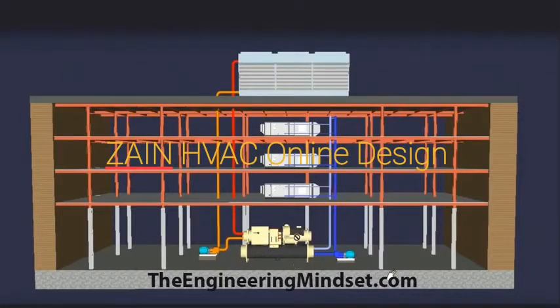Just to run you through this again. So here we've got the evaporator on the bottom of the chiller, and that's where the chilled or the cold water is produced. So that chilled water is then pumped up through the riser, and then taps off of there, enters the floor, and then enters into the AHU, and we're going to be looking at how that gives off its coolth there. So that cold chilled water will be entering into a coil inside there, and the water then returns through that into the riser.